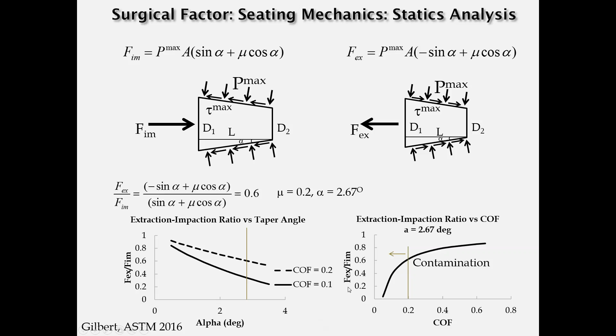In addition, we've recently been investigating how the mechanics of seating may influence the properties and the fretting corrosion reactions at the taper interface. One such test is the seating mechanics test shown here. What we do is we basically apply a sort of quasi-static ramp loading to the head, while also monitoring with two non-contact displacement sensors the relative motion of the head to the neck. And shown are two graphs, one where we're seating only to 100 newtons of load, and another one where we're seating to 4,000 newtons of load. That should be 4,000, not 40,000, apologies there.